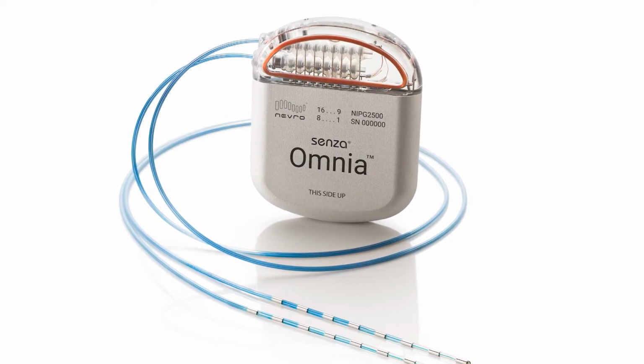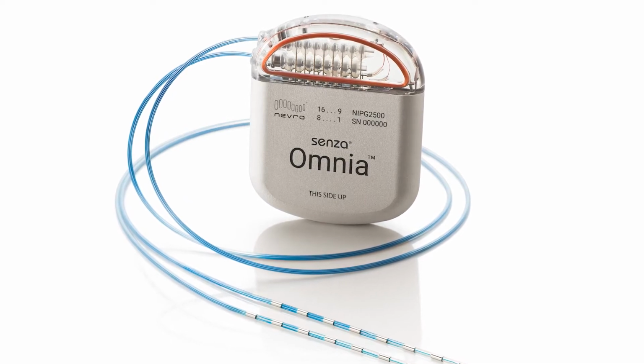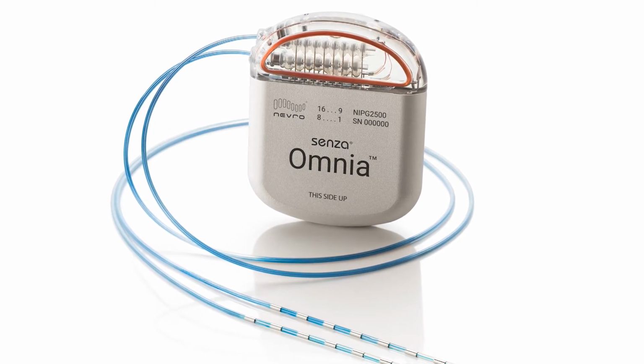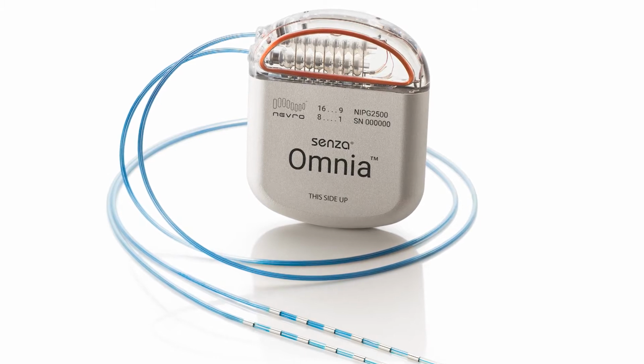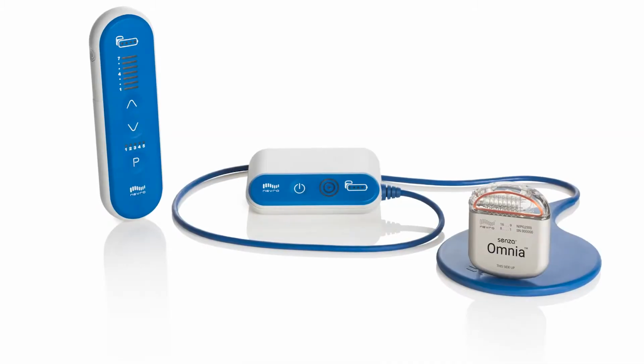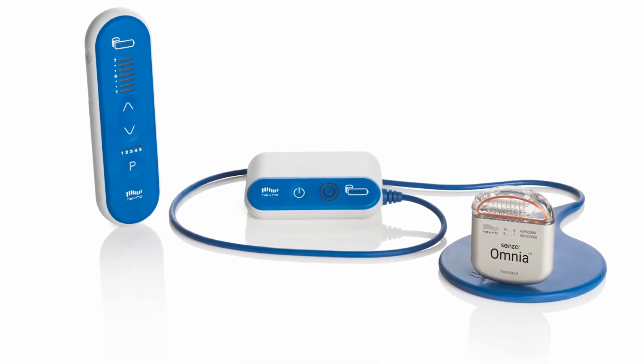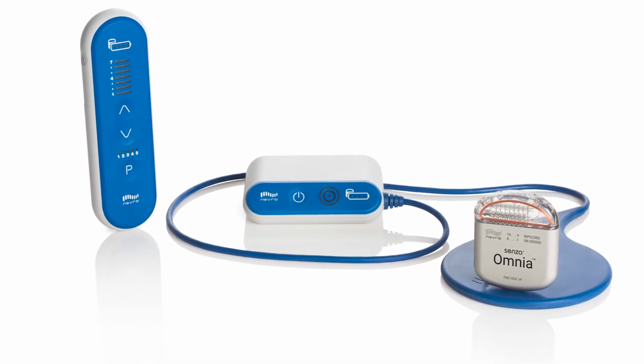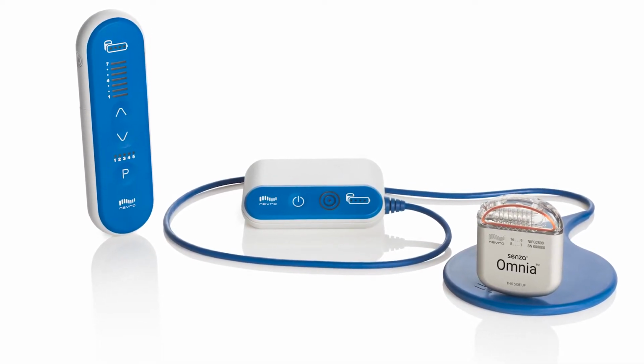All spinal cord stimulators are classified as traditional except Nevro. Nevro is the exclusive manufacturer of HF10 therapy. HF10 therapy is the only spinal cord stimulator that does not produce these abnormal tingling sensations whatsoever. HF10 uses a proprietary 10,000 hertz. Traditional spinal cord stimulators go to a maximum of 1,500 hertz, or cycles per second. This therapy runs at 10,000 hertz. Therefore, you do not feel the stimulation.